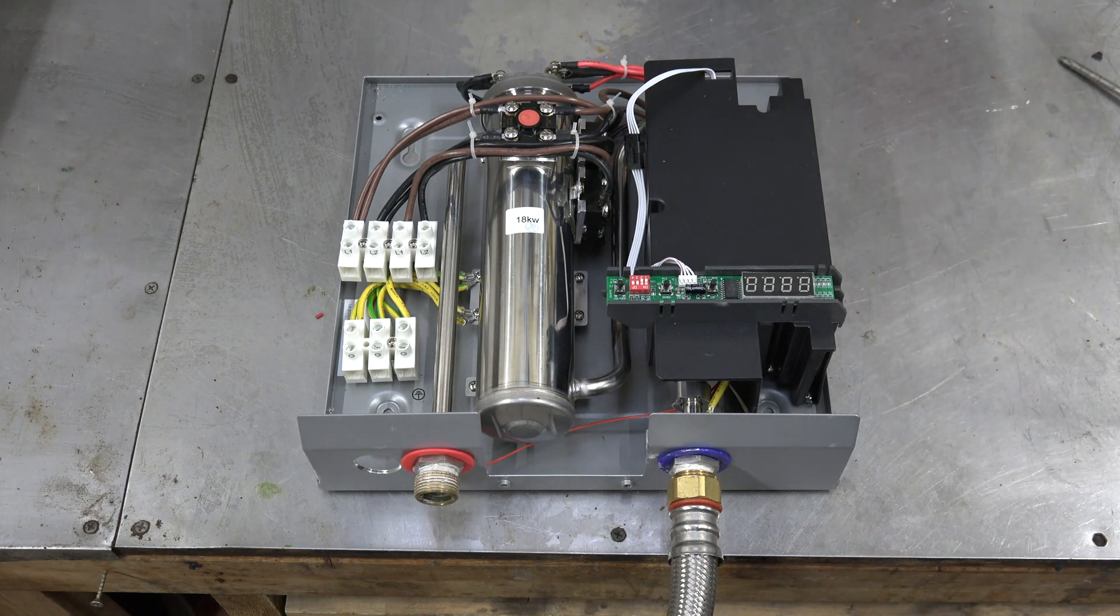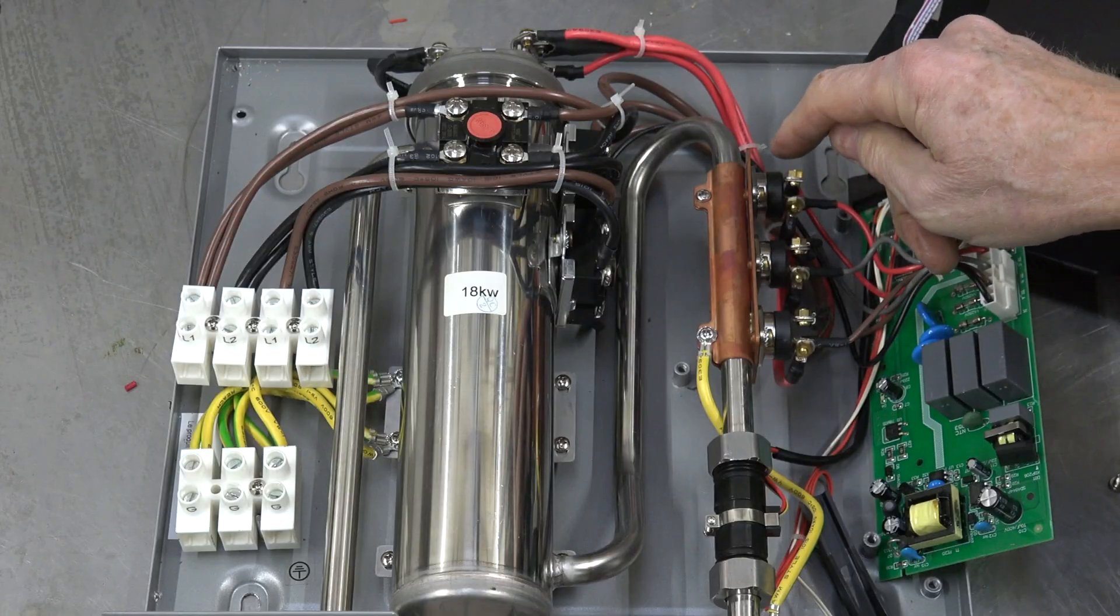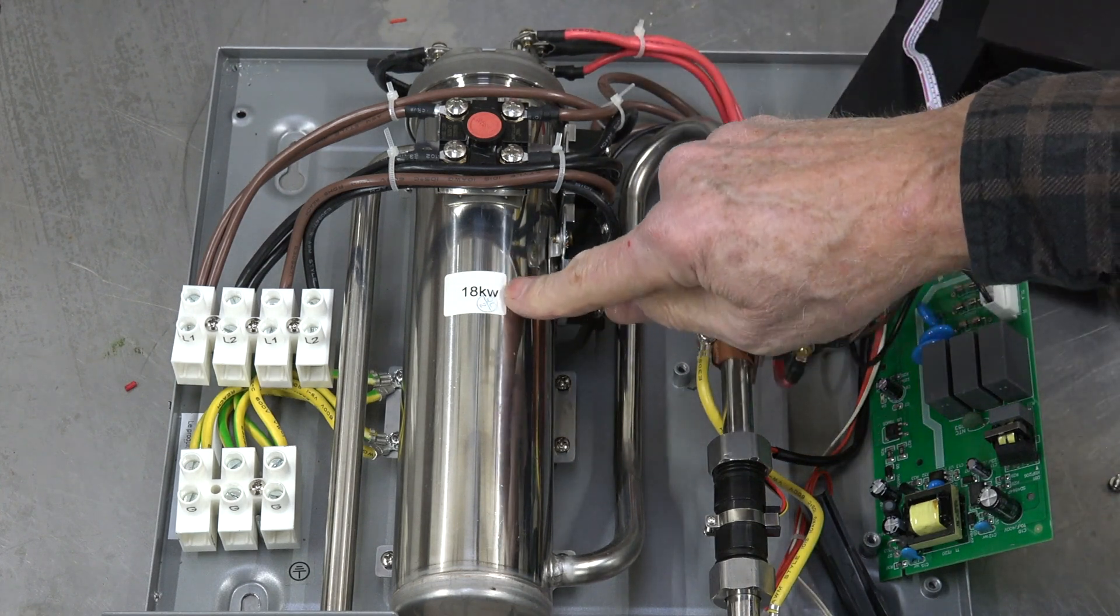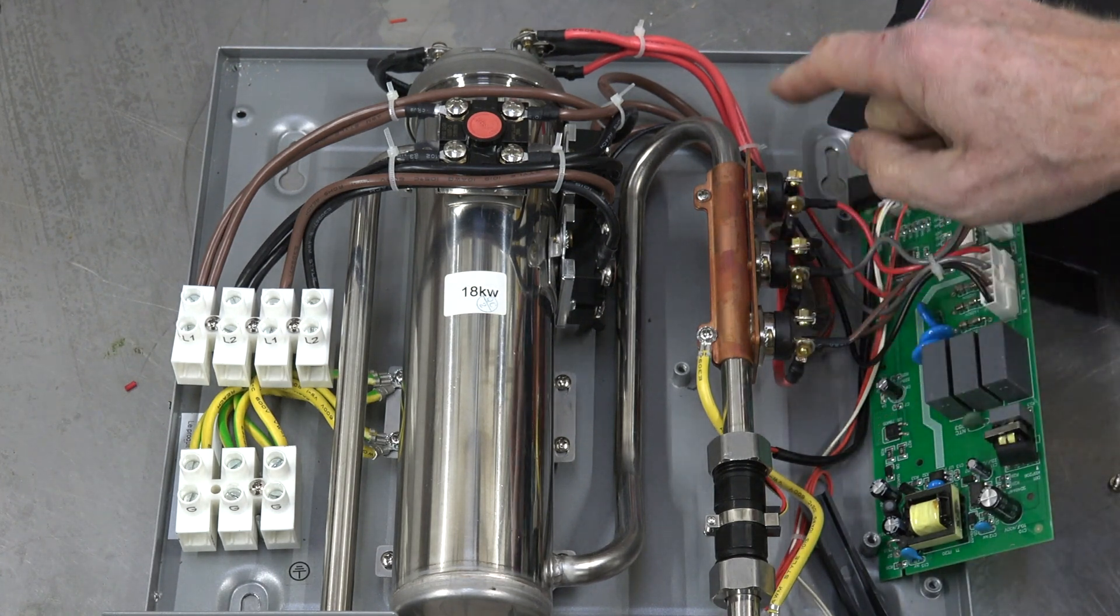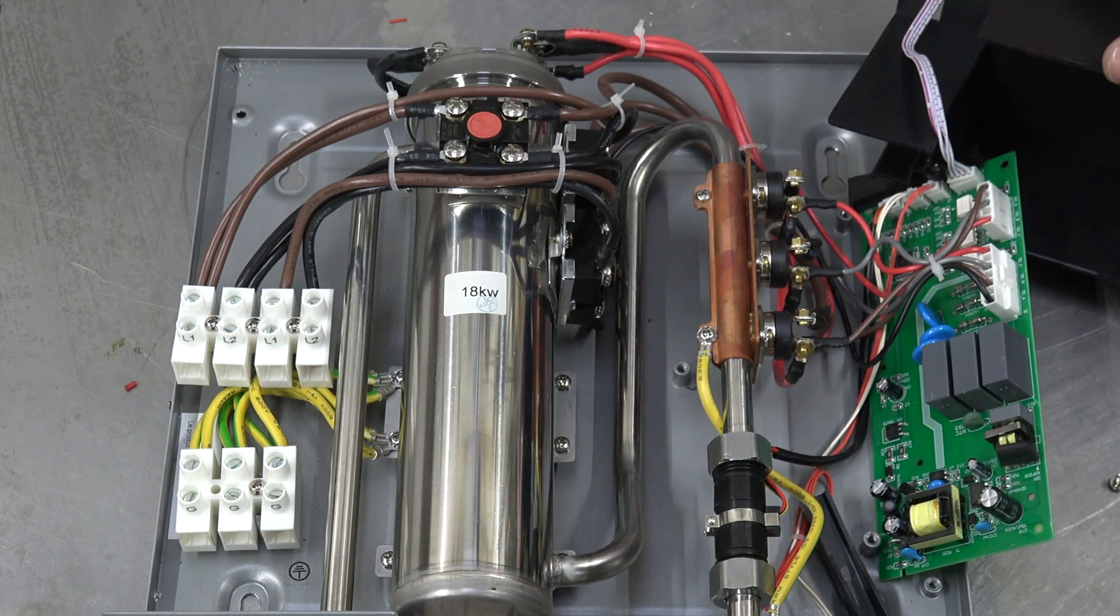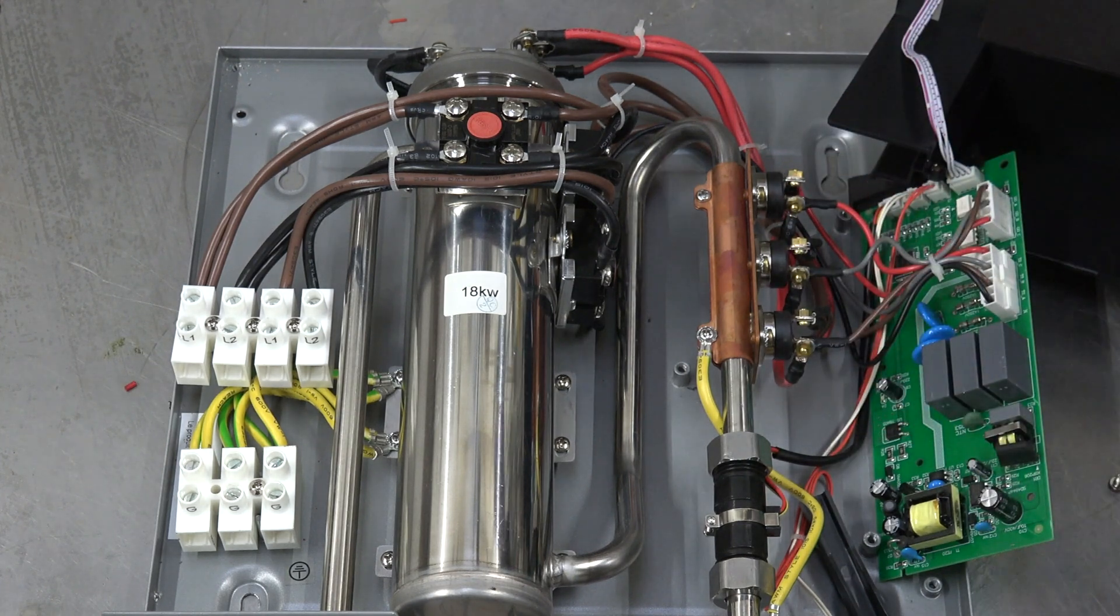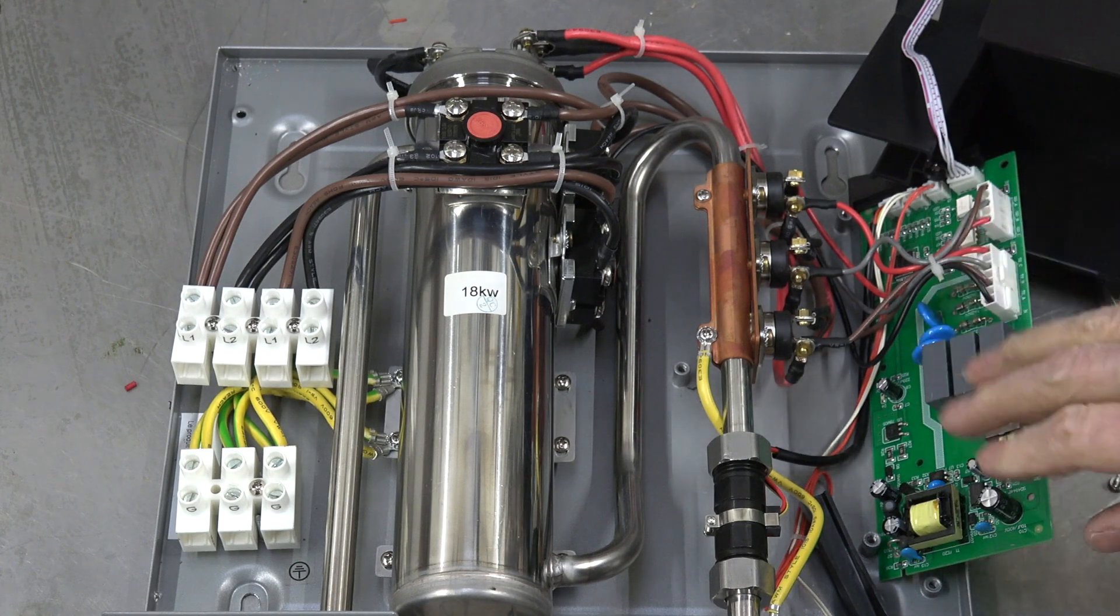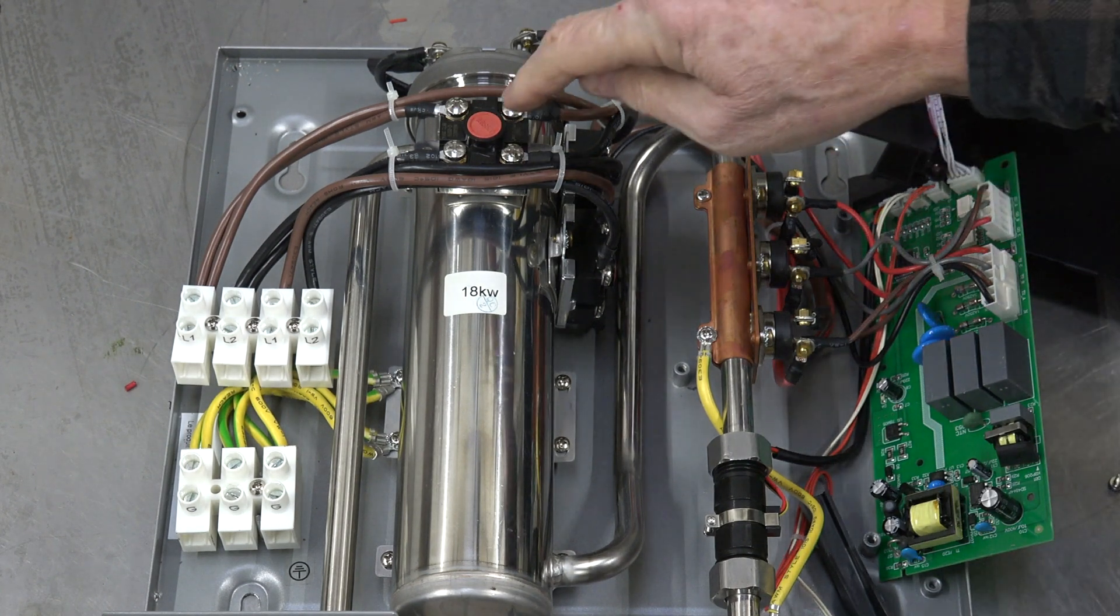So looking at this thing with the cover off of it, we've got three switches there. Those are the control switches that turn the elements on. Remember I said there were three elements, 18 kilowatts, six each. These are the shutoffs. If there is water flowing through it, it allows the elements to come on through these switches and they will heat until they get to the proper temperature that you've set, and then the electronic board shuts them off.